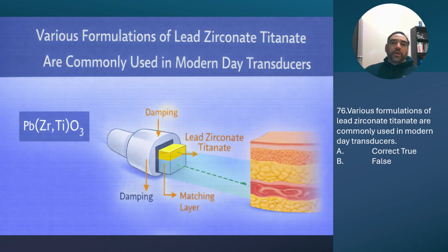All right. And if again we're looking at this, and let's say you initially think of this as incorrect, so let's walk through that rationale. Again, if this were false, it would suggest that PZT is not commonly used, which again that's just flat out incorrect. PZT is the most widely used piezoelectric ceramic in medical ultrasound. It's engineered again in various formulations for optimized performance for a particular type of scan.